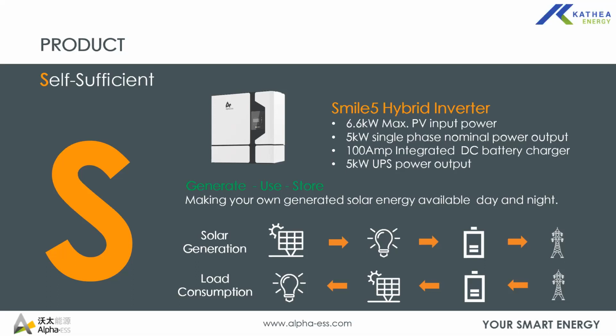So it can utilize your PV, and you can also use your grid to charge your batteries in cases where you have an upcoming load shedding and the irradiance is quite low. Then you can quickly set it to charge from the grid. We'll also look into those settings in detail. It's a 5 kilowatt single phase, so you can back up your system with a 5 kilowatt uninterrupted power supply. The inverter has a 20 millisecond changeover when it loses grid.